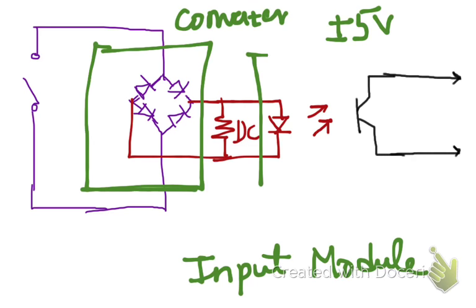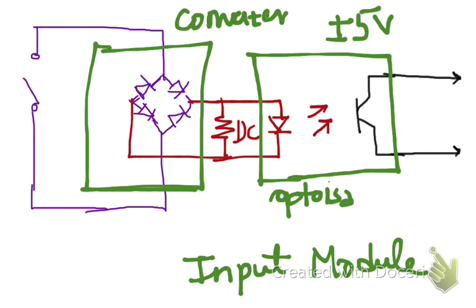And what you are seeing next here is an optical isolator or an opto isolator. What an opto isolator does is, it converts the electrical signals it receives here into light signals. The major advantage of this is that, if your electrical signals directly go into the CPU, it might cause any damage. To avoid that, what this optical isolator does is, it converts these electrical signals into light signals. So these signals, whether they are on or off, they are carried by using a light beam. So this light beam is produced by an LED or a light emitting diode.